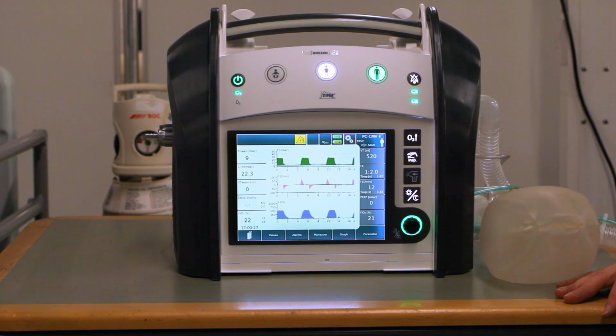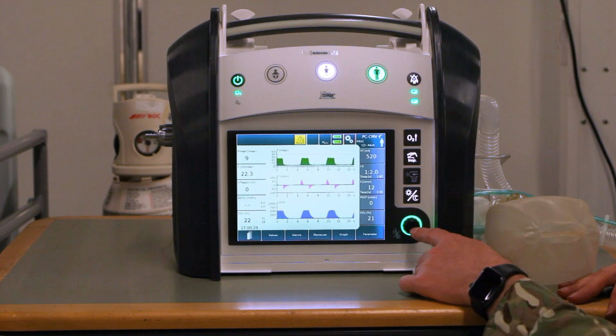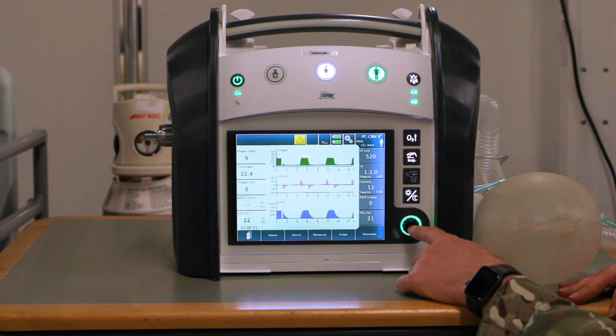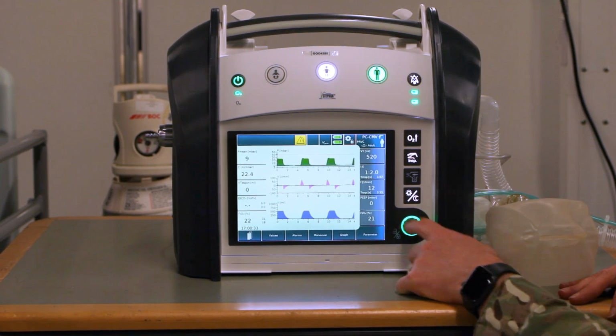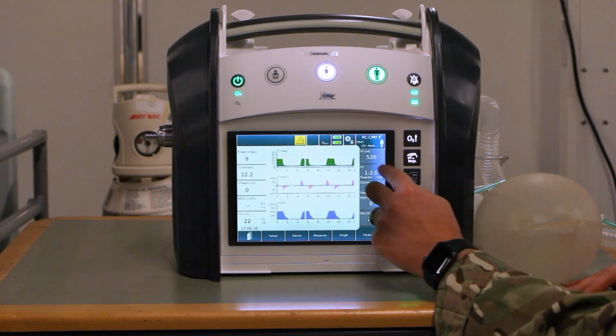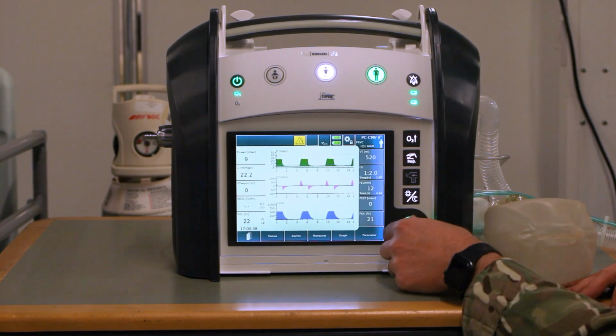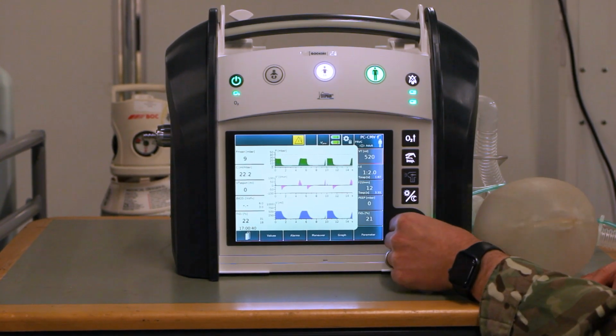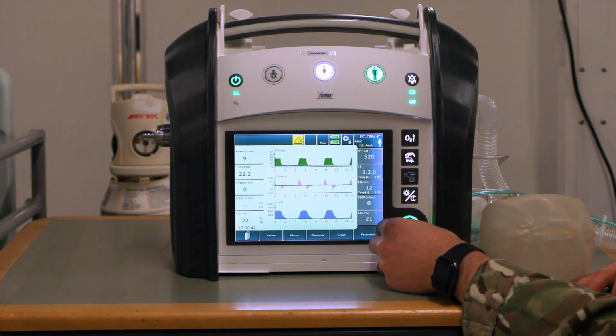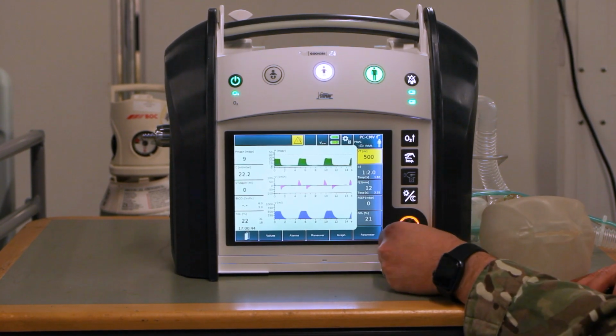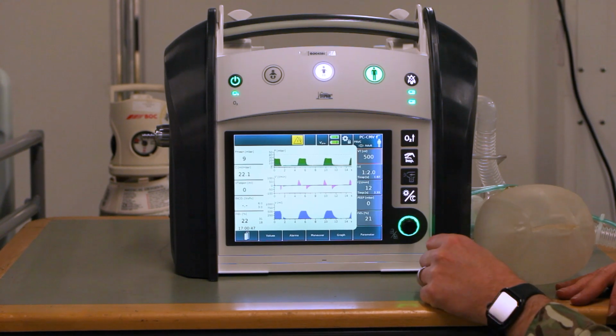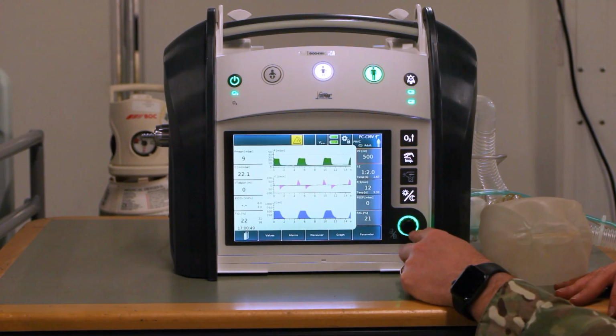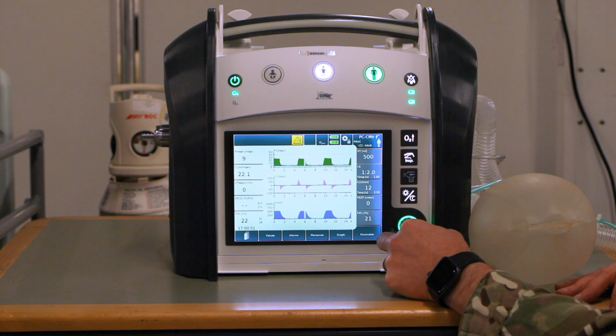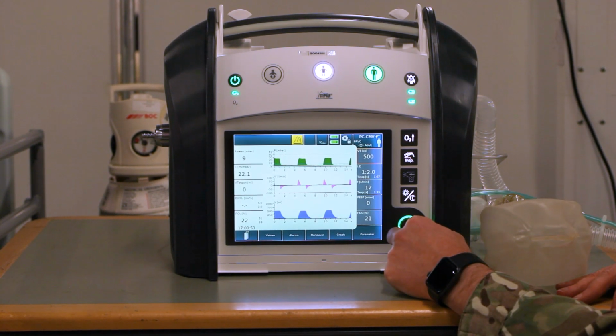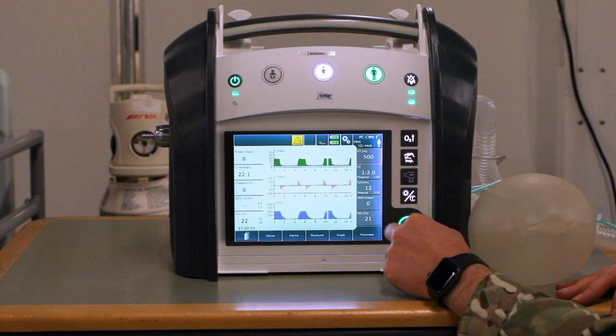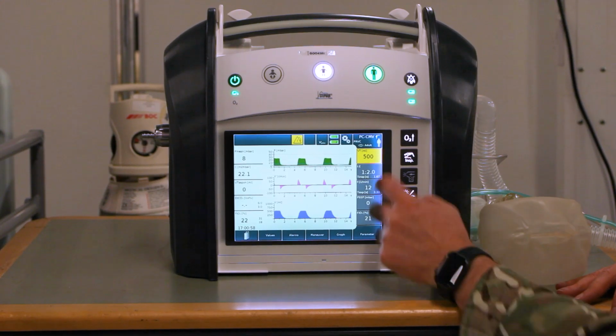If doing a transfer, you may want to lock the touchscreen: press and hold the knob for 3 seconds. This will put a lock on here, and now the touchscreen is not active. If you do want to change a setting, you can still twist the knob, click on it, make your change, and then confirm the setting by pressing the knob again. To remove it out of lock for the touchscreen, press and hold the knob for another 3 seconds, and the touchscreen is now active again.